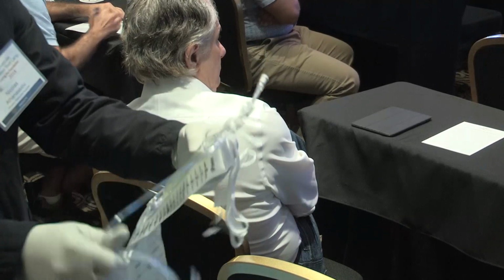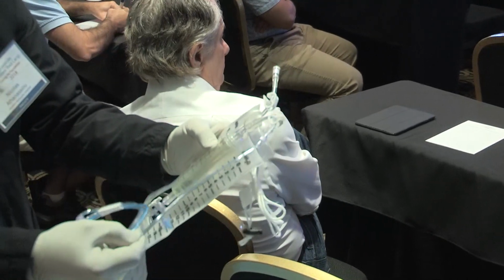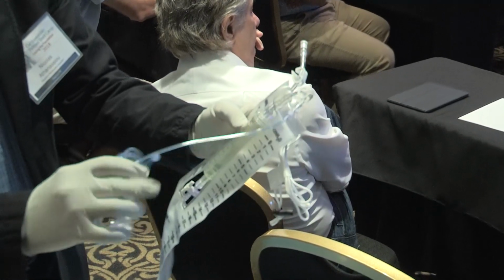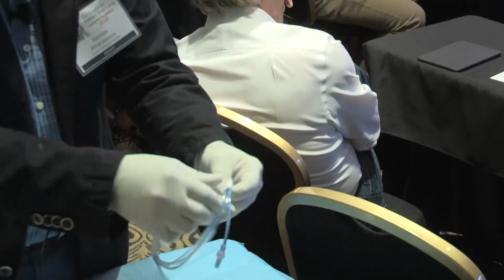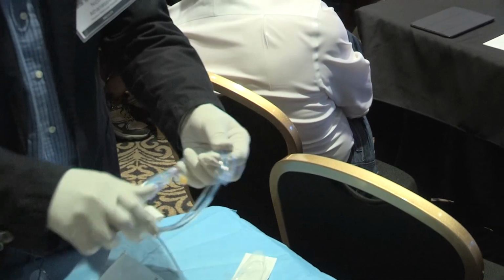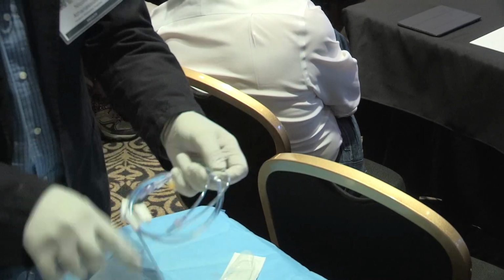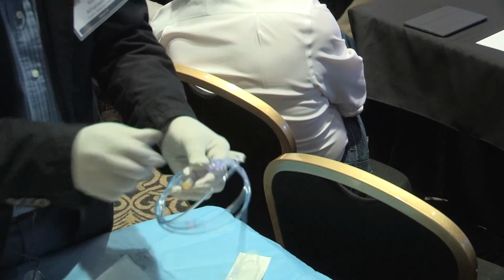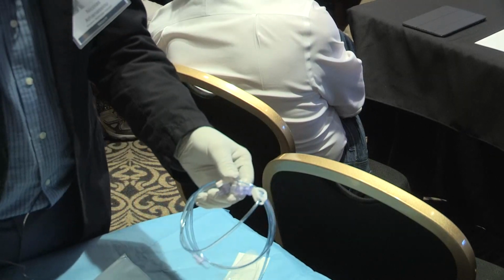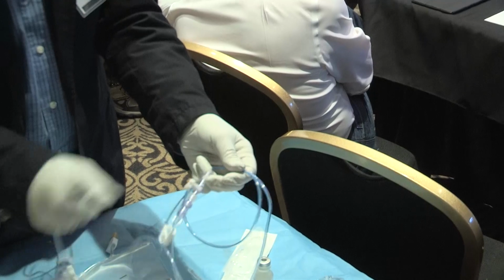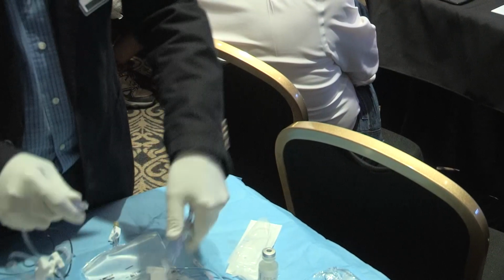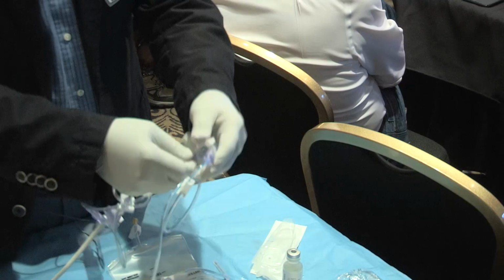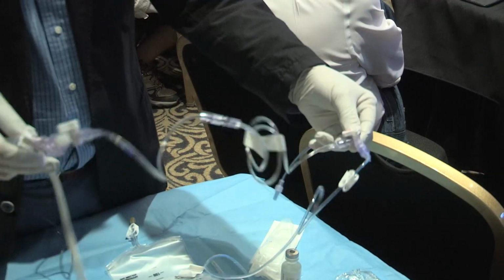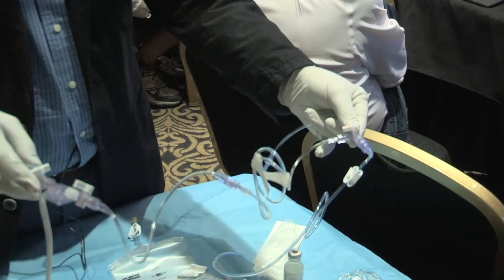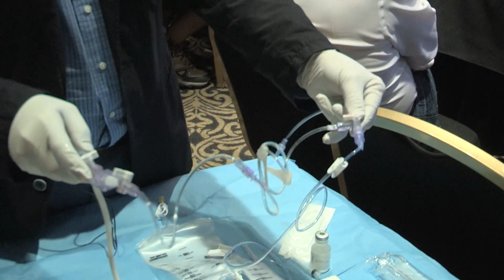So this is how it comes from the kit. It has this tube here, which is blue, and basically blue means to the patient. So from the patient to the bag. It has a three-way, which, let me just tear this off. This three-way has a little cap that you take off, and that's where you need to connect your transducer. So the three-way can open to drain from the patient into the bag. So this is how this is connected. This is the transducer, and this is the flushed pressure line.